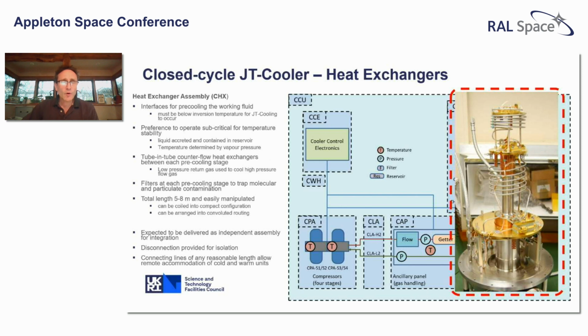We have a preference to operate our coolers subcritical, so we accrete liquid in the reservoir, and the temperature is then determined by the vapor pressure. The tube-in-tube counterflow heat exchangers you see run between each cooling stage, and they're there to use the low pressure gas returning in the line to cool the high pressure line.